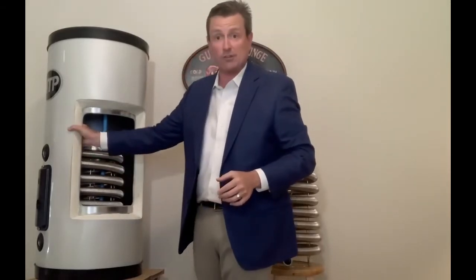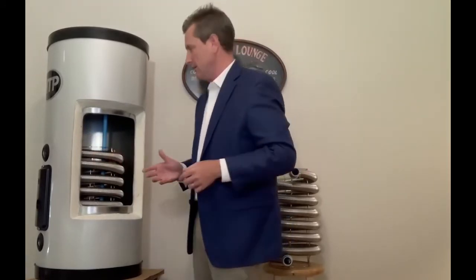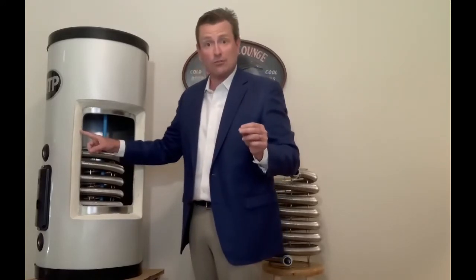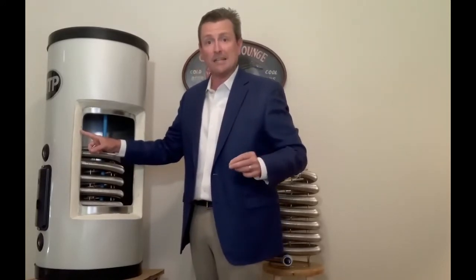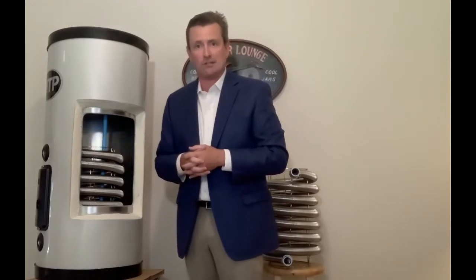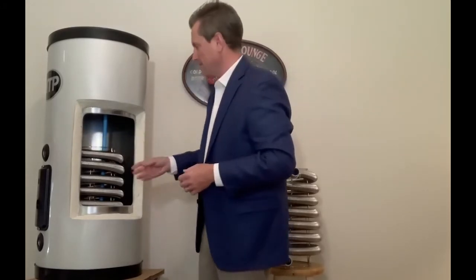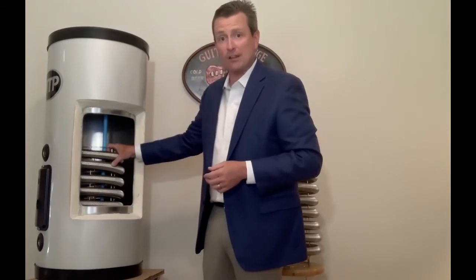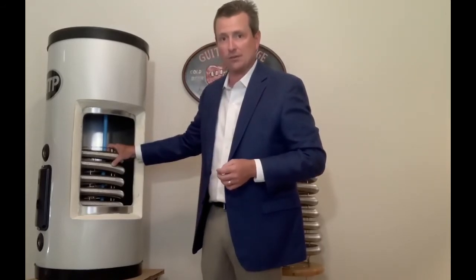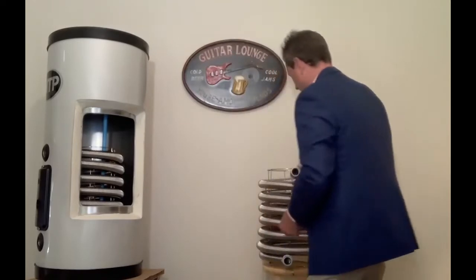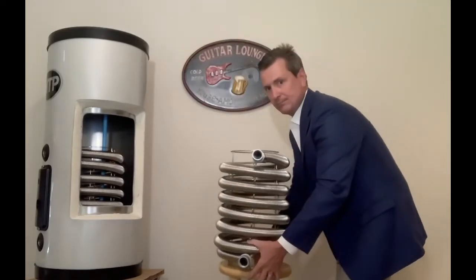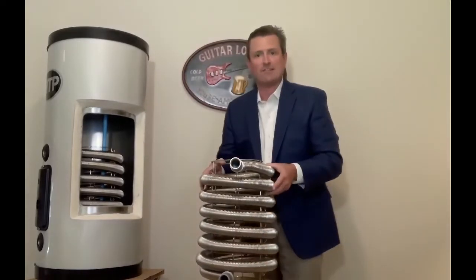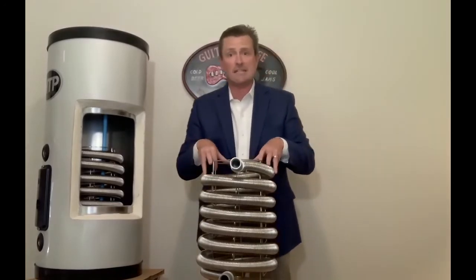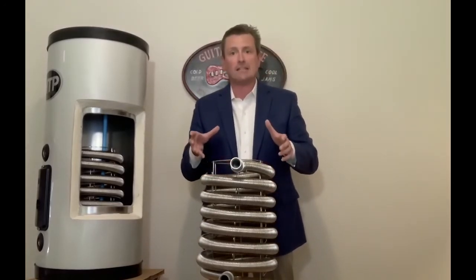Now, the construction of the indirect is still 316L stainless steel, a high quality marine grade stainless, just like the SuperStor that you know and love. Over 2 inches of blown foam, high density insulation, very low standby loss, less than half a degree an hour. And behind there, we have our SuperFlex heat exchanger, the key to all of the success with this product. So what is a SuperFlex heat exchanger? A SuperFlex heat exchanger is a 316L corrugated stainless steel heat exchanger.